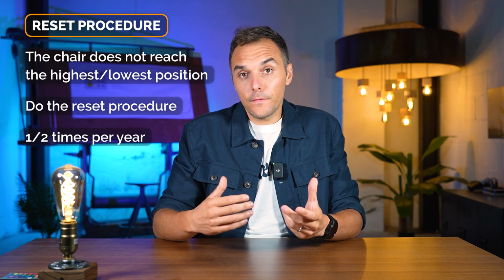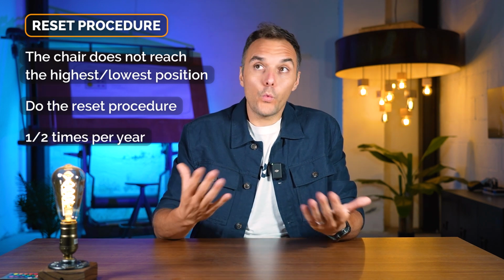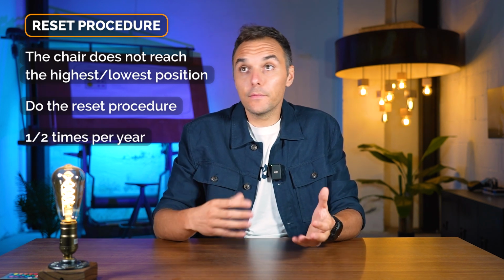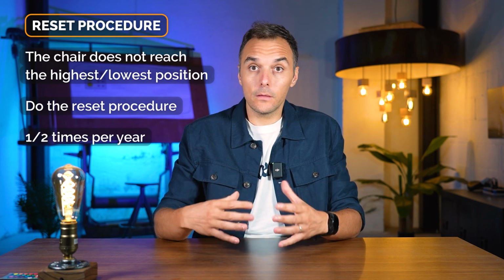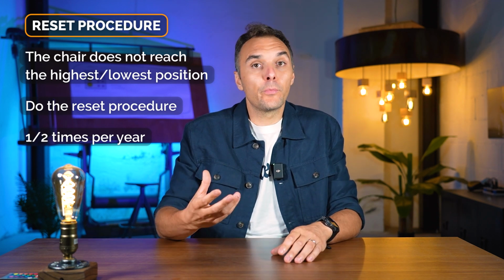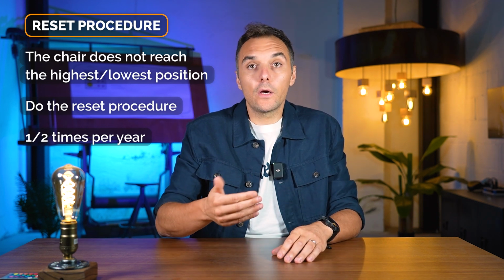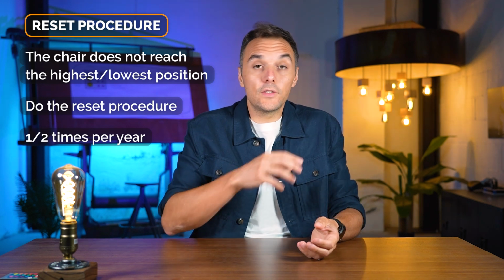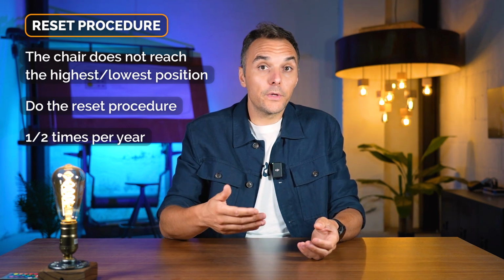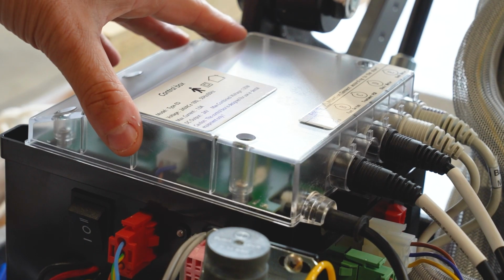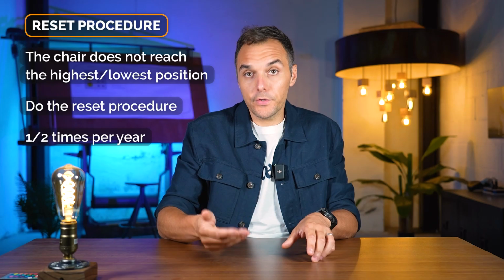This reset operation can be done once or twice per year if there's some fault in the electrical system of the clinic, but it's not something you should do every week or every day. If this problem happens frequently, we need to replace the main board at the chair base, since that's what's causing the issue.